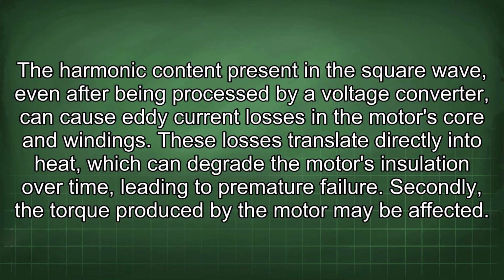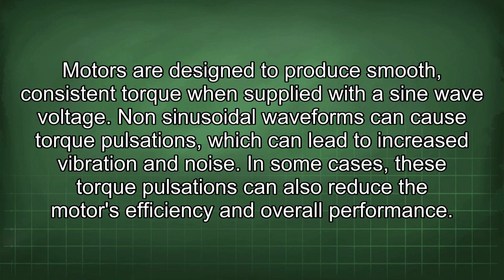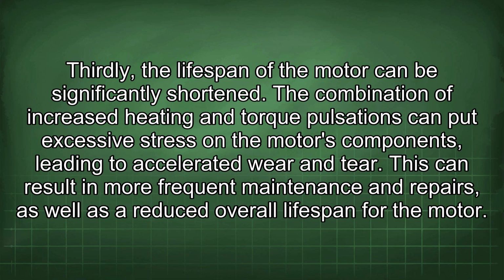Secondly, the torque produced by the motor may be affected. Motors are designed to produce smooth, consistent torque when supplied with a sine wave voltage. Non-sinusoidal waveforms can cause torque pulsations, which can lead to increased vibration and noise. In some cases, these torque pulsations can also reduce the motor's efficiency and overall performance. Thirdly, the lifespan of the motor can be significantly shortened. The combination of increased heating and torque pulsations can put excessive stress on the motor's components, leading to accelerated wear and tear. This can result in more frequent maintenance and repairs, as well as a reduced overall lifespan for the motor.